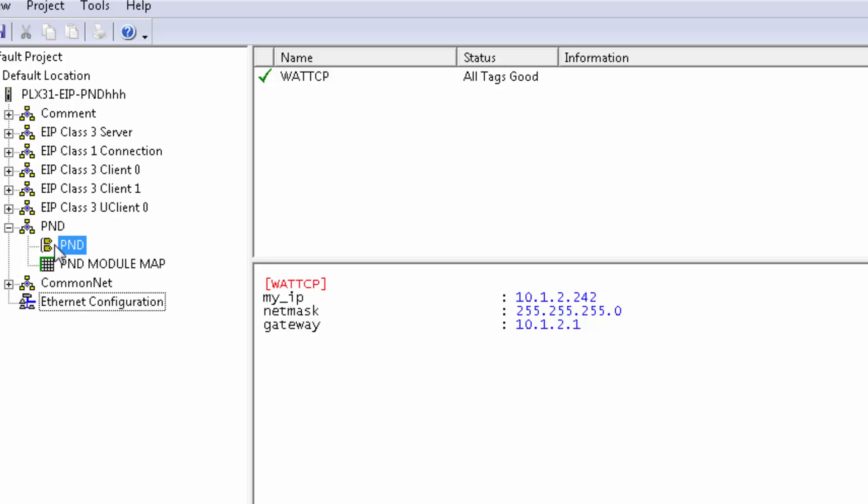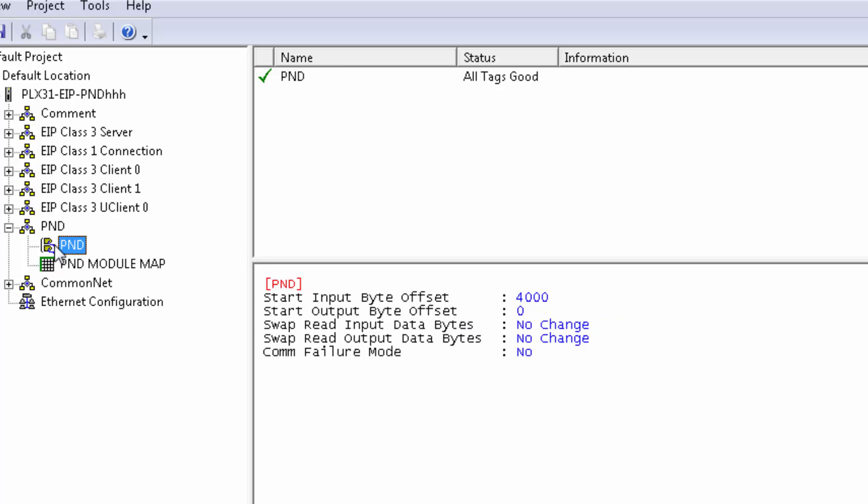So expand PND and then click on PND, and here you can see the input and output for the byte offset inside our database. A byte is half a word, so the input byte offset of 4,000 is word 2,000, matching up to our EIP output of 2,000, and the output of 0 matches our EIP input of 0.